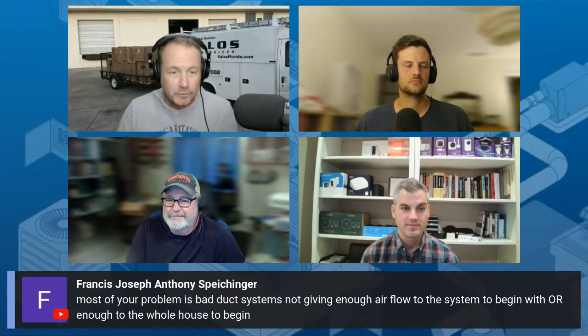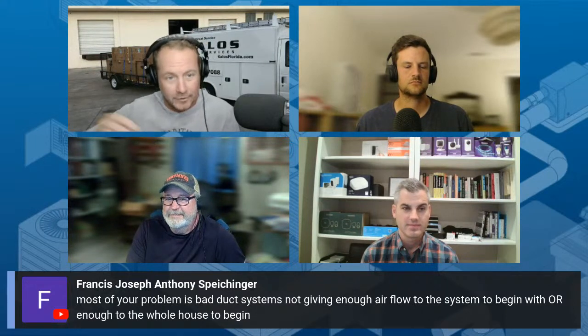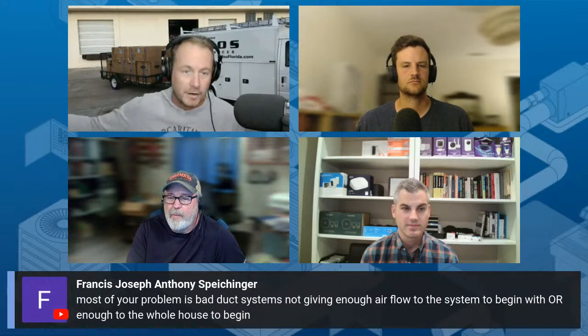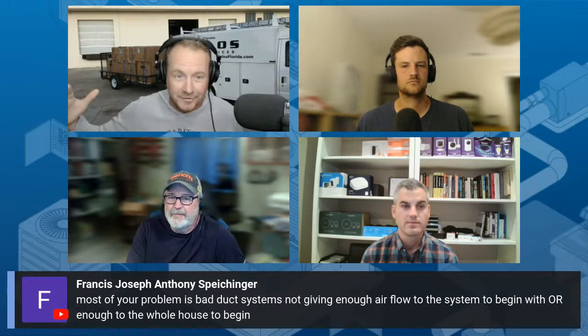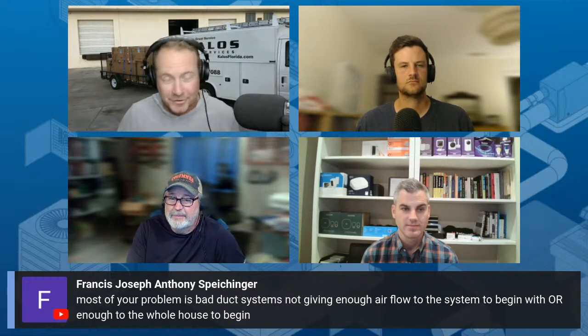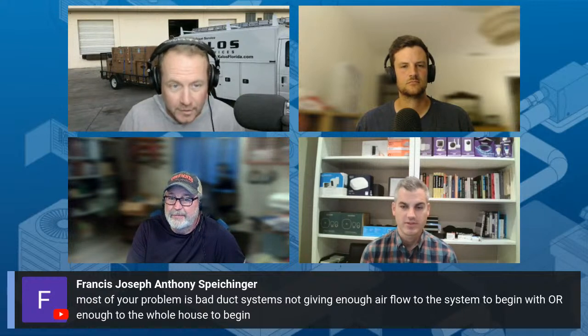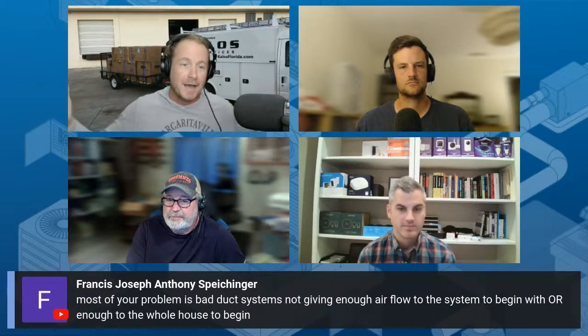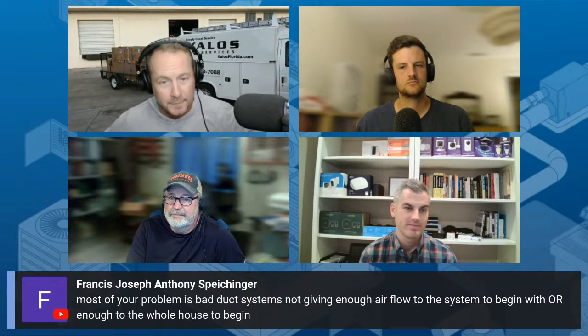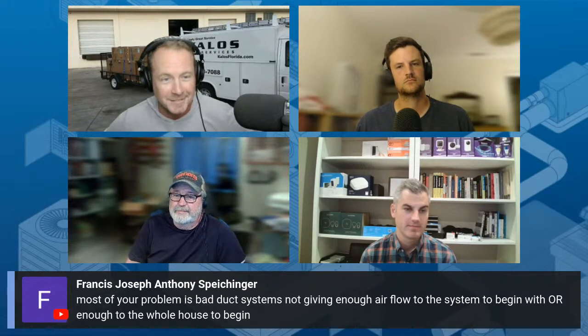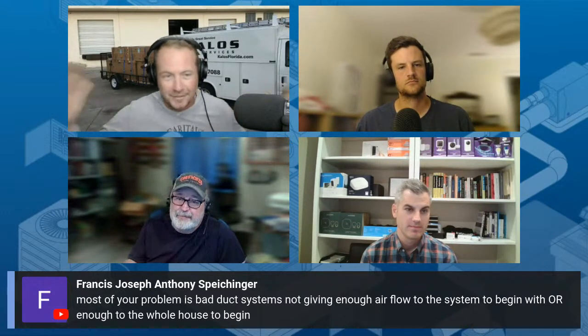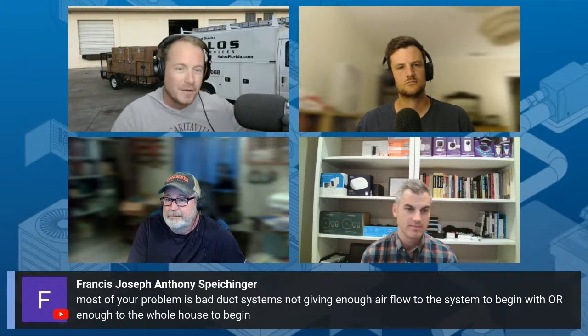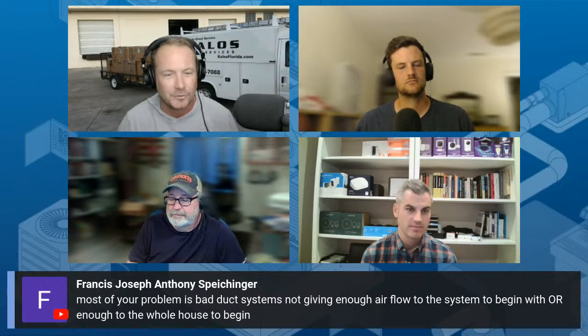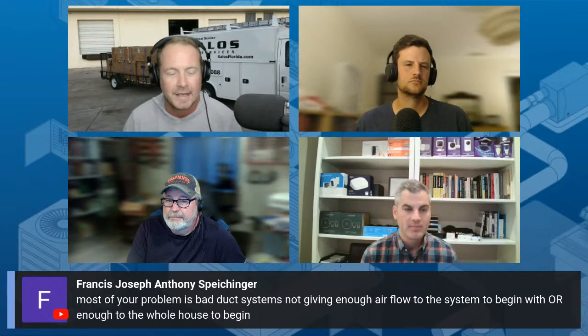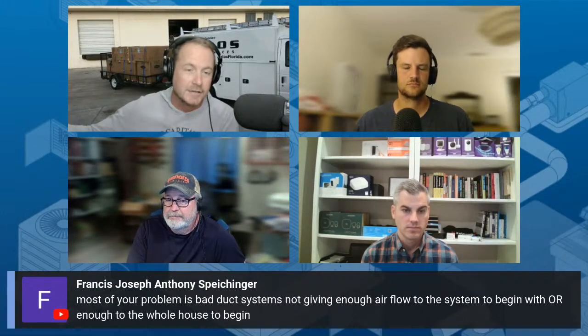Well, literally what you're doing is you're driving up your head pressure. That's what you do when you run lower airflow over your condenser, and now your condenser is the indoor coil. You're driving up your head pressure, which does what to your compression ratio? Increases it. What happens when you increase your compression ratio? Less capacity, less efficiency. So the easiest, simplest, most magical way to get more capacity and efficiency out of a heat pump is to run really good airflow over both of your coils, which means efficient use of defrost, and nothing impeding anything: no dirty filters, no bushes clogging up the outdoor unit, no snow on it or anything like that, and running high airflow, as high as you possibly can on the inside.